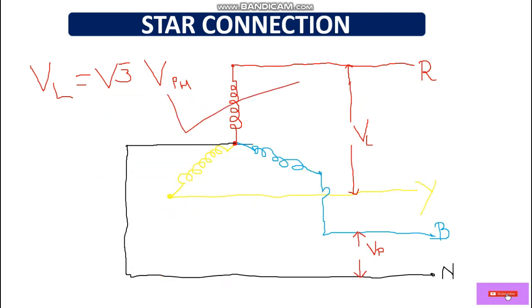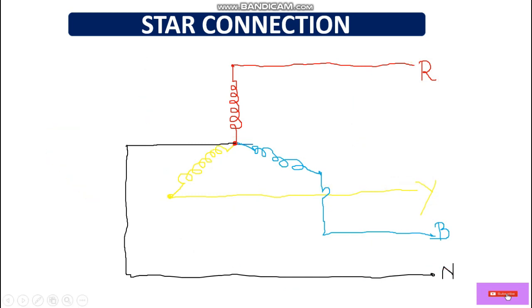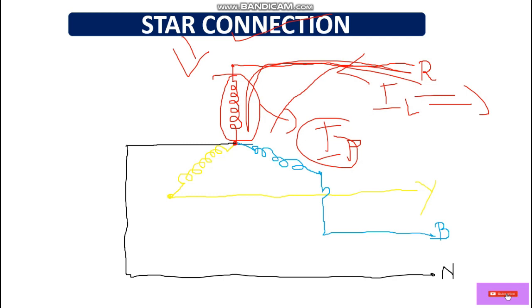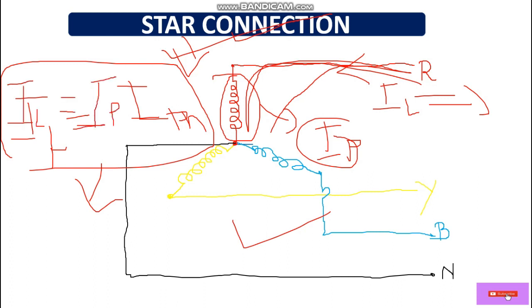Always remember: the voltage measured between two phases is called line voltage, and the voltage measured between a phase and the neutral point is called phase voltage. To calculate phase voltage: V-phase equals V-line divided by root 3, so 415 divided by 1.732 equals 240 volts. In a star connection, line current equals phase current — both are the same.